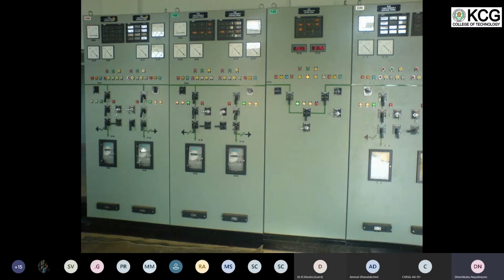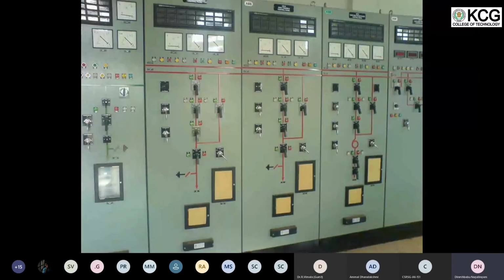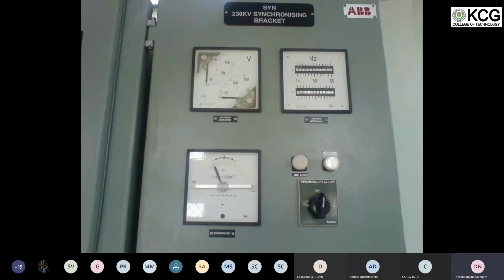So let me move on. More control panels, 230 kV side panels, synchronization panels. Okay. So we have been doing this in lab on dark lamp method, bright lamp method, like this different ways. So what we do in synchronization is we have to verify same voltage, same frequency, and same phase angle. Then only we can close the breaker, so that both sides of the breaker should be synchronized to ensure that, we have this synchronization panel.